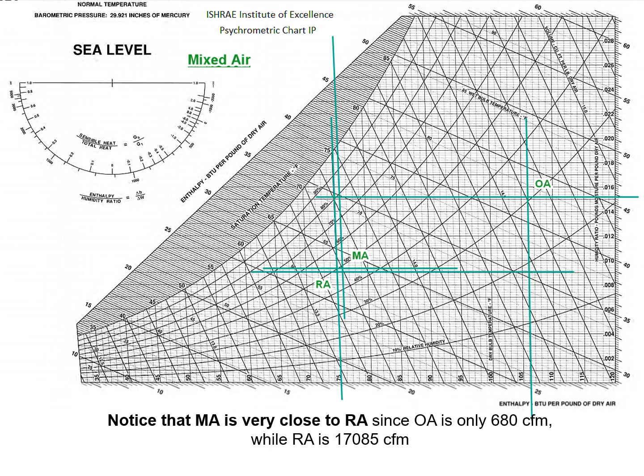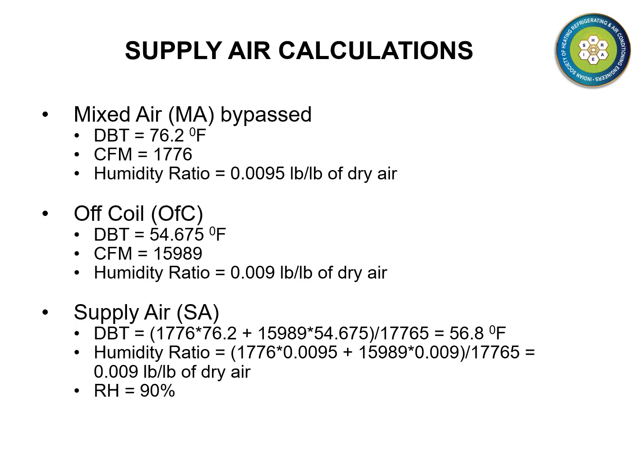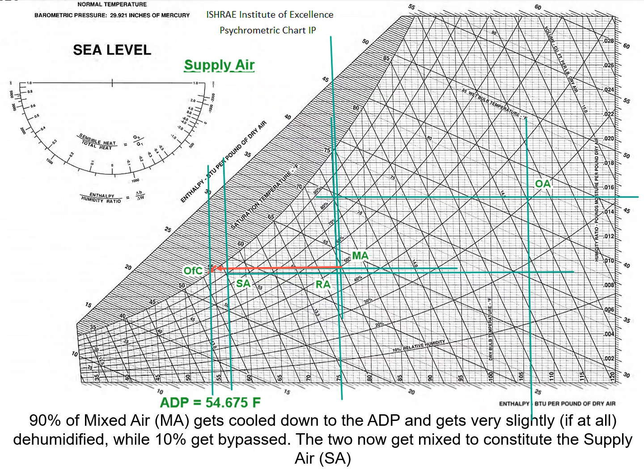Supply air calculations are shown on this slide. Again, pause the video and carefully go over the calculations. In this slide, we have mapped the off-coil condition OFC as well as the supply air condition, that is SA. Notice that 90% of mixed air gets cooled down to the ADP while 10% of it gets bypassed. The two get mixed and constitute the supply air SA.